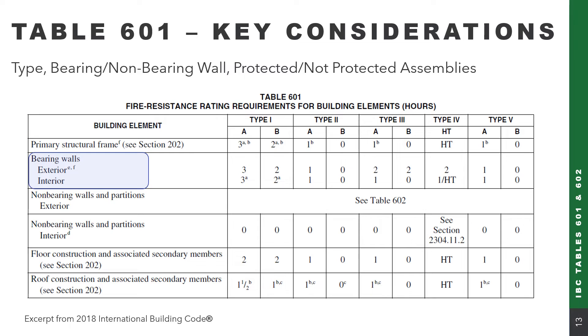Table 601 covers bearing walls, which can be exterior or interior. Going across the row, for the most part the requirements are the same whether a wall is exterior or interior — with one notable exception: Type 3 construction, where exterior walls still need to maintain two hours for both 3A and 3B, whereas on the interior it drops to 1 hour or 0 hours. Also, for an interior wall of Type 4 heavy timber construction, it drops down to a 1 hour or heavy timber type wall.